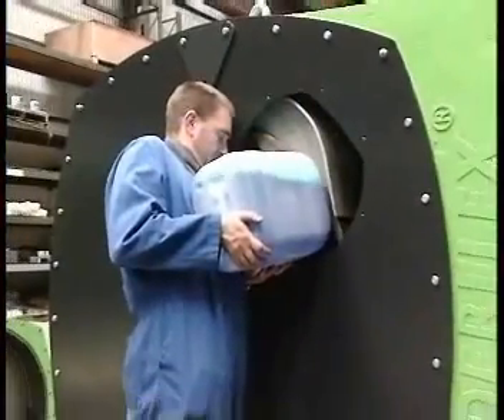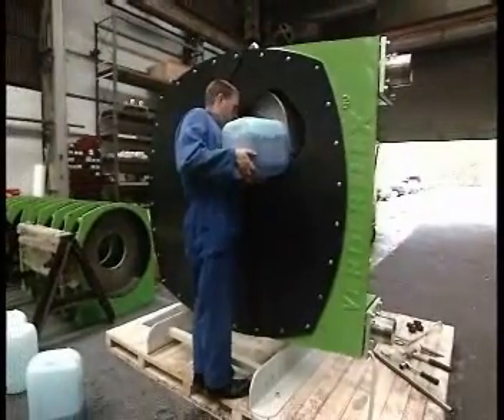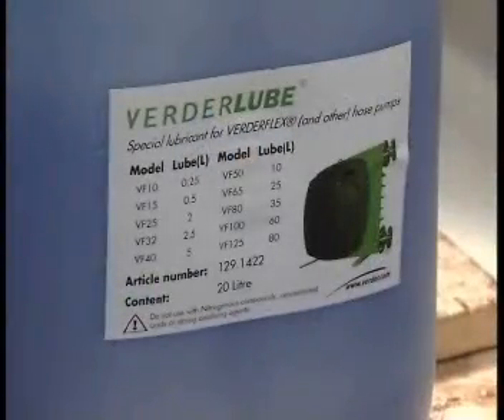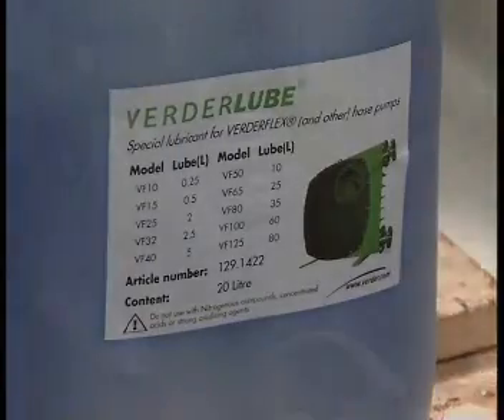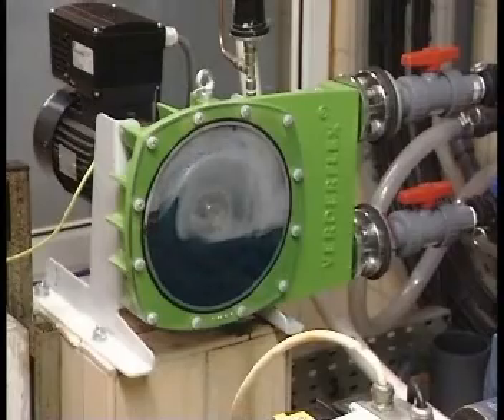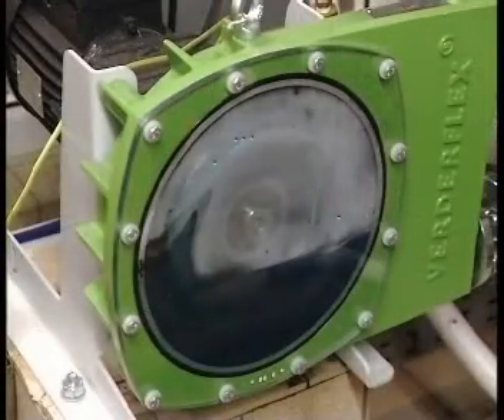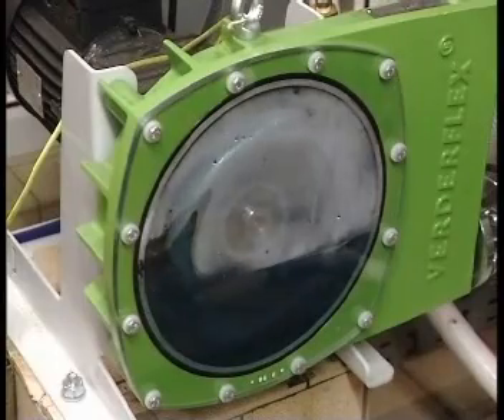The pump casing is partially filled with VerderLube lubricant, specially formulated to cool the pump and ensure long hose life. A major advantage of this design is that the VerderFlex pump is fail-safe. Should product leak from the hose, it is still safely contained within the pump casing.